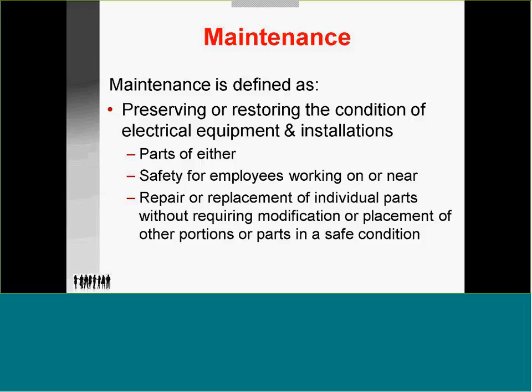Maintenance is critical and is defined as preserving or restoring the condition of electrical equipment and installation, or parts of either, safe for employees working on or near, including repair or replacement of individual parts without requiring modification or replacement of other portions of parts in safe condition. So what it is, we've got to make sure everything we're putting in is right for it. If something goes wrong and you change a breaker, it should be the manufacturer-recommended breaker used in that particular situation.